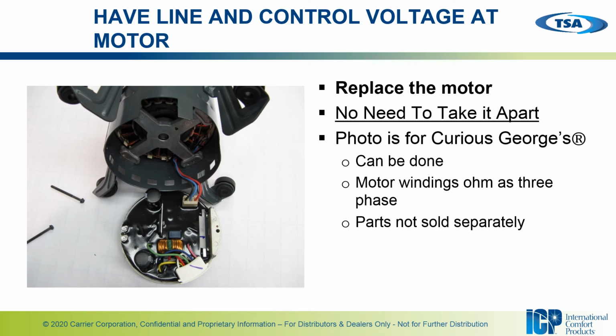So what do we do if you have line voltage and control voltage at the motor? In this case, you are going to replace the entire thing. They are sold as one piece. So there's no need to take the control module and the motor apart for any further diagnostics. Although it can be done, it's sold as one piece, so it really isn't going to make a difference.